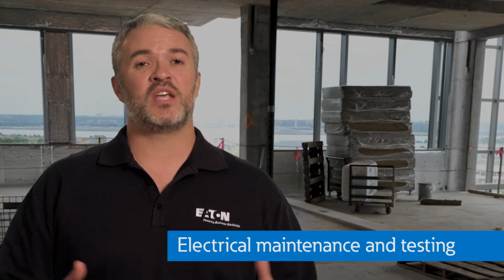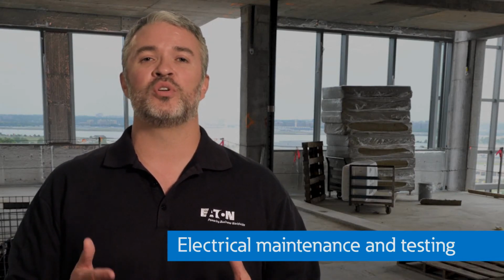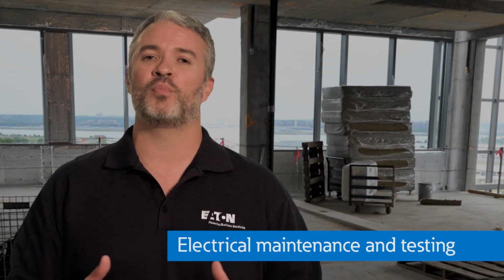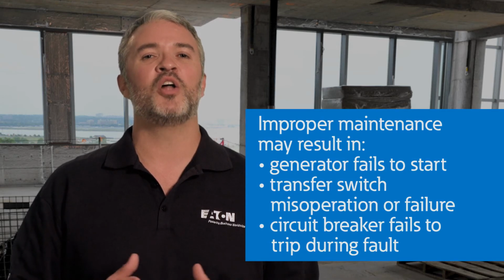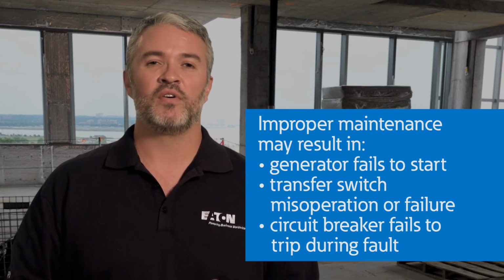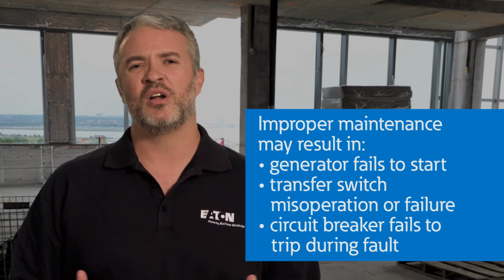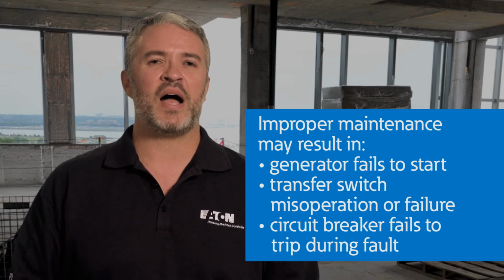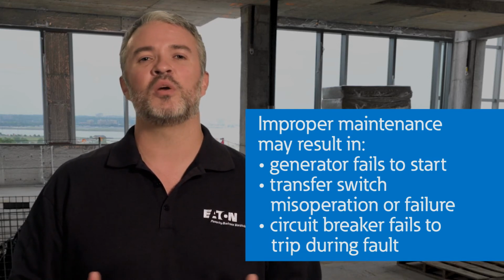Electrical maintenance and testing in a healthcare facility is crucial to ensuring equipment is going to perform properly and make the overall electrical system safe and reliable. Without proper maintenance, there are a lot of unwanted situations that might occur. For example, a generator doesn't start, transfer switches can't transfer power during an emergency, or even a circuit breaker doesn't trip during a fault. Healthcare environments are all about reliability.